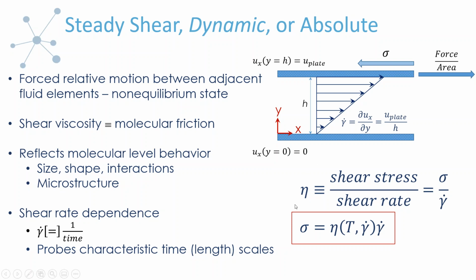So as we talked briefly at the very intro there, it's a proportionality between shear stress and, in this case, shear rate, which is the appropriate way of quantifying the deformation in a steady shear flow. And so what is that shear rate for this simple flow configuration? I'll just take an opportunity to repeat some of our previous content. The idea behind rheology instrumentation is that because you're often studying very complex fluids, you want to set up as simple a flow field as possible. So rheometers are designed to have simple flow fields to facilitate the calculation of the rheological properties. And so this is probably the most simple one, and it's probably the best to illustrate.